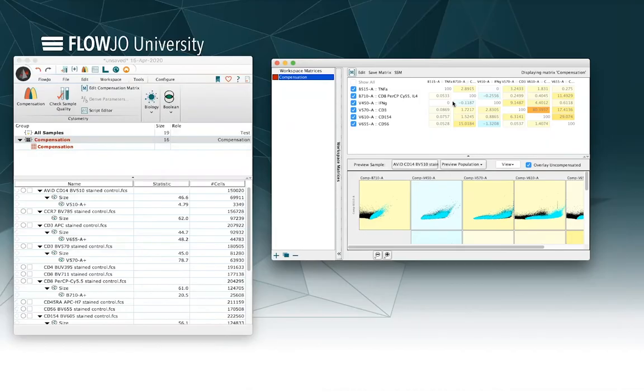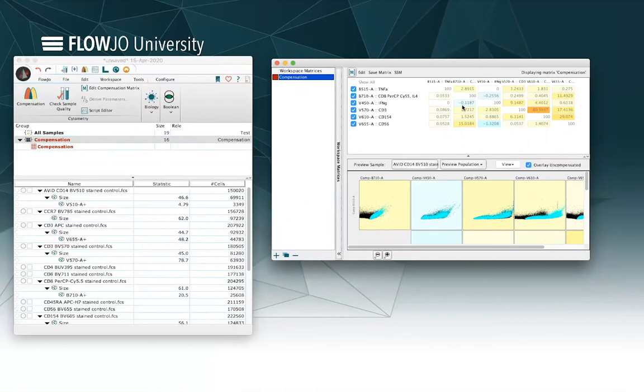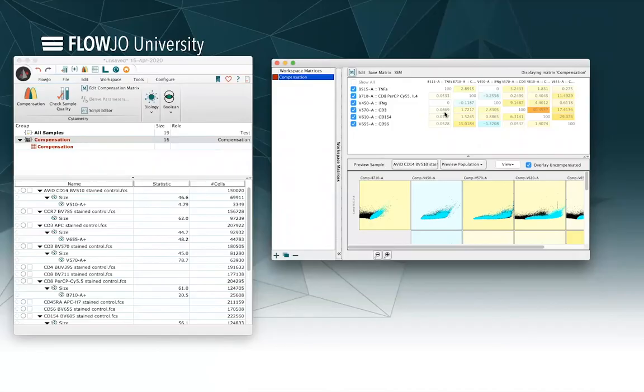Each of the columns here is the detector and each of the rows here is a different color that's spilling into that detector to some degree or another. If you notice some negative values in there, as long as they're fairly low that is pretty normal and kind of expected. If you see values that are getting higher here, that just means that you have some bad spillover maybe occurring between a particular parameter and its associated detector in the columns there.